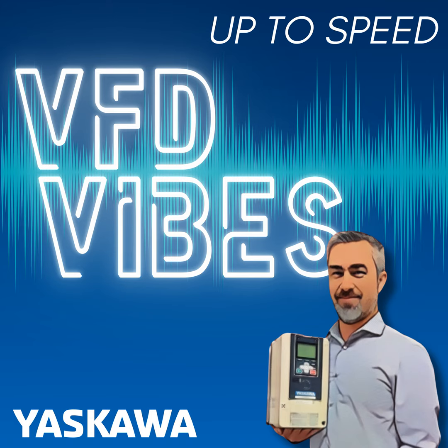You've already hit on overvoltage as one of the top faults that you've heard in tech support. What are some of the other big ones out there? Yeah, probably OL2, a drive overload where we're exceeding the rated output current of the drive. That could be a big variation of causes. One of the big ones was probably the low impedance, high efficiency motors in HVAC applications. Now I'm talking Z1000 and now HV600, our current flagship HVAC drive.